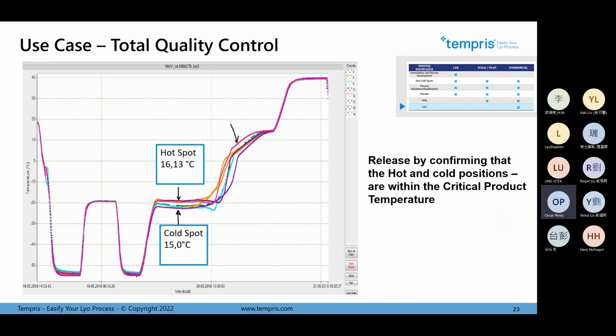But of course, why would you want to measure in 40 positions? Why are we not playing with the system, identifying the critical positions in the freeze dryers, where maybe 8 sensors or 15 sensors are enough for your large freeze dryer? Because we want to identify the hot and cold spots inside the freeze dryer. By measuring these points, we can identify whether our product during the cycle is going through this design space. At the end, thanks to measuring these critical positions, we will have the top temperature and the lower temperature during the whole cycle.